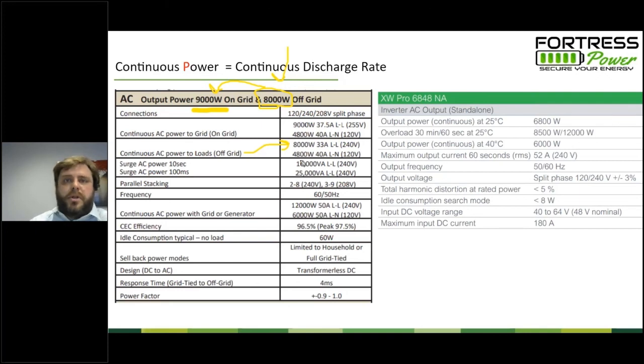Well, the inverter will enact its own protection mechanisms, and after a period of time, usually about 1 minute, it'll turn off. Now, this particular inverter has a little bit more flexibility put into it. It gives you a little bit more power output in grid tied mode. So you could put 9 kilowatts of load on it, and then maybe a little bit less when you're in the off grid mode of operation.